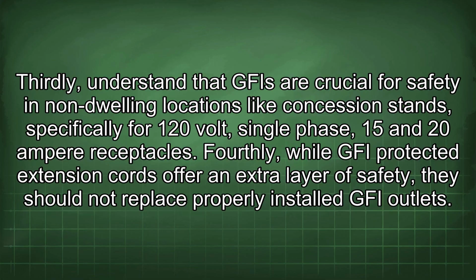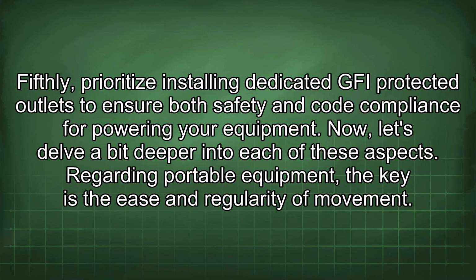Thirdly, understand that GFI are crucial for safety in non-dwelling locations like concession stands, specifically for 120-volt, single-phase, 15 and 20 ampere receptacles. Fourthly, while GFI protected extension cords offer an extra layer of safety, they should not replace properly installed GFI outlets. Fifthly, prioritize installing dedicated GFI protected outlets to ensure both safety and code compliance for powering your equipment. Now let's delve a bit deeper into each of these aspects.